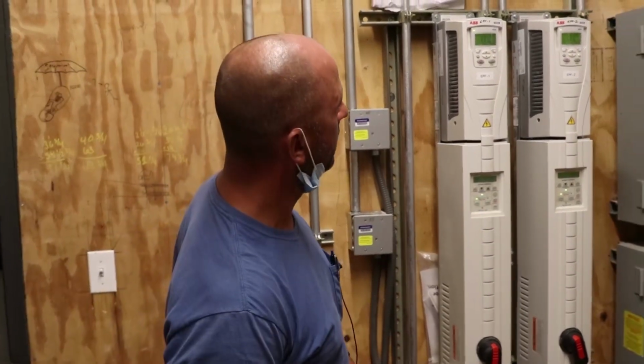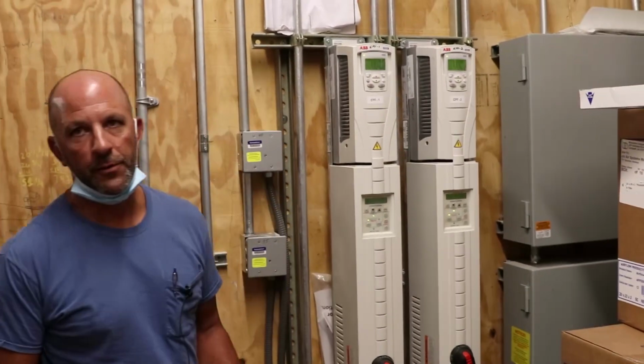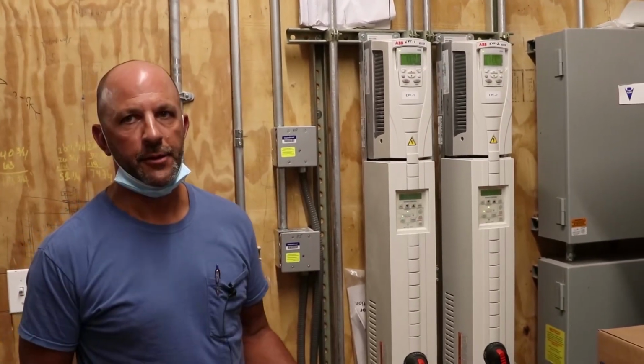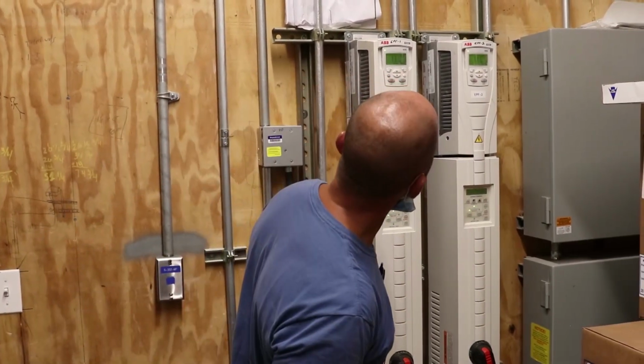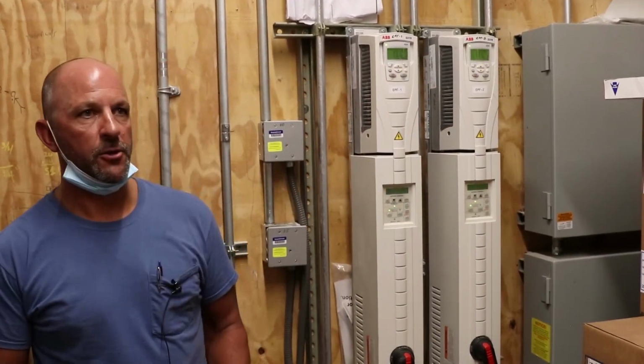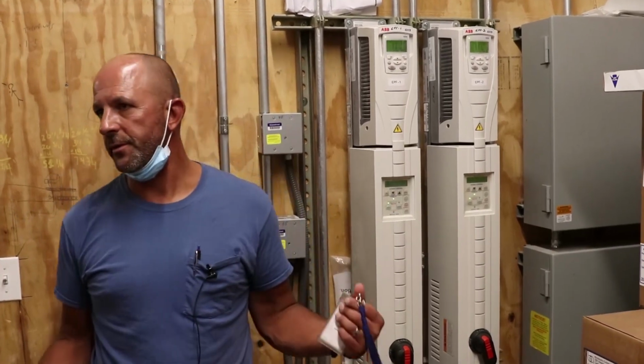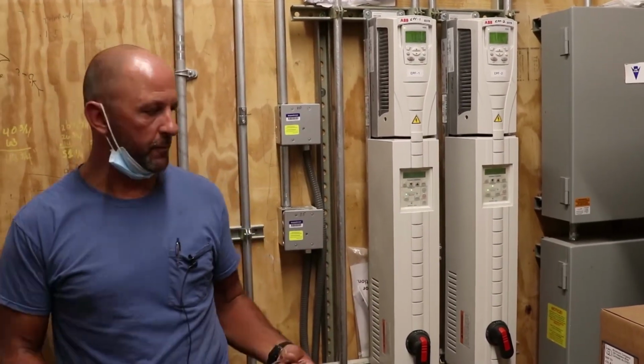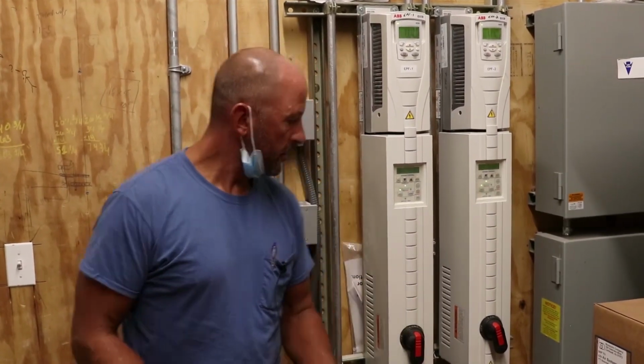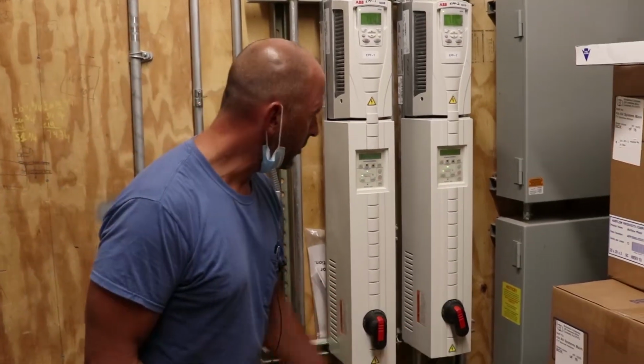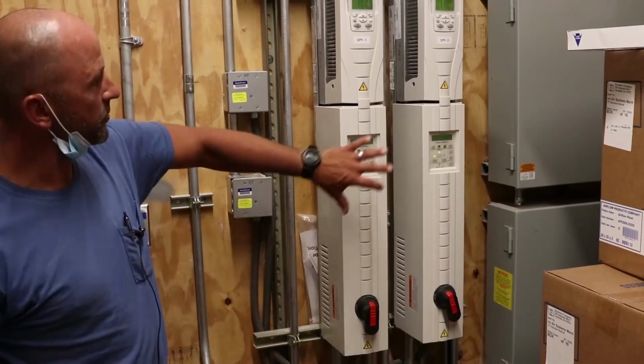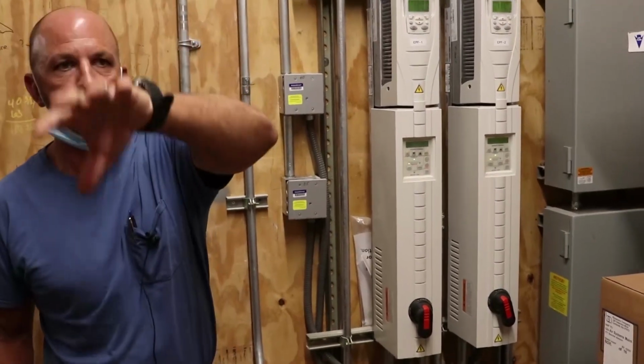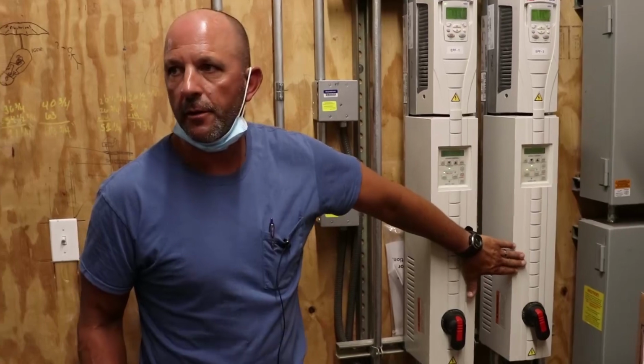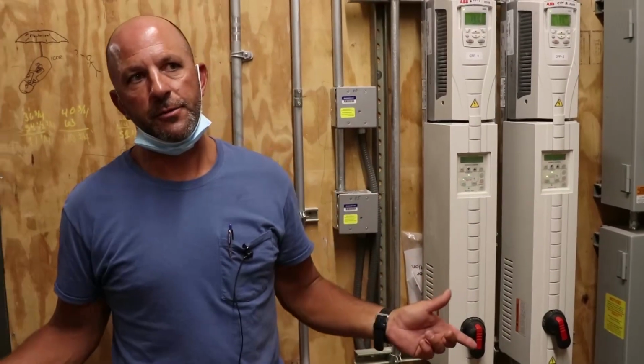These were all set by we read these out, so you're not gonna see them run to 60 hertz. You're gonna see some other number. I'm not sure exactly what the number is, but when they start, you're not gonna see them go up to full speed, because at full speed, it's like a hurricane in there. So they oversize them and then you scale them back on the drive just to get it positive. Local disconnects. I'm not going to get into the drives too much, but that's what those 2 elevator pressurization fans are. This is where the controls and the drives are. We can hit the 5th floor. I can show you the other ones, the drive controls, and I think that's pretty much we covered it.